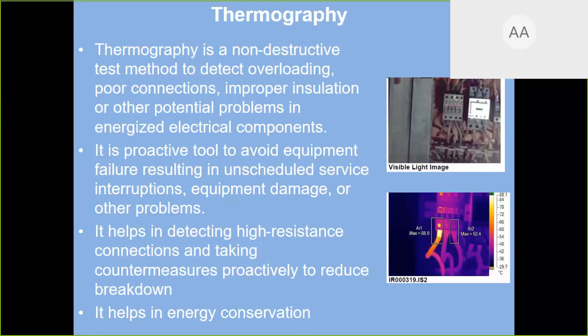Each panel should be checked with thermography, not only one, each panel, whether it is HT or LT or DB, distribution board. Each DB, if you check, you will find out there is no overloading, no poor connection, no improper insulation. Then no different color will be shown in the thermography. It will show like this. All the colors will be the same. It means my thermography is okay. So my dear friends, these are some of the tools which can prevent fire.